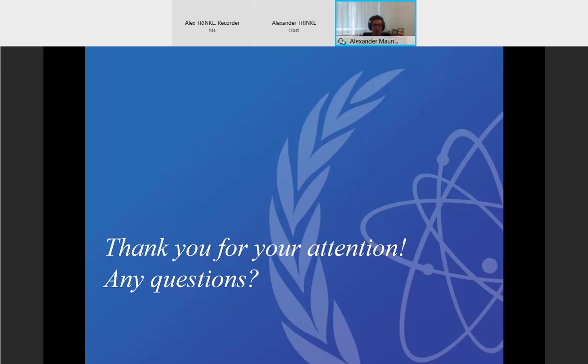Which I guess kind of goes back to a previous question about the performance differences between P-type and N-type. I forgot to mention that N-type detectors are the better choice if you are using it somewhere where there's a chance of a neutron flux hitting your detector. Furthermore, for high activity, high count rate applications, I recommend not having the sample so close to the detector, maybe move it a little bit away, because it will give less summing and less need for correction for summing, while the activity is still probably high enough that you get enough of a spectrum without having to measure so long.